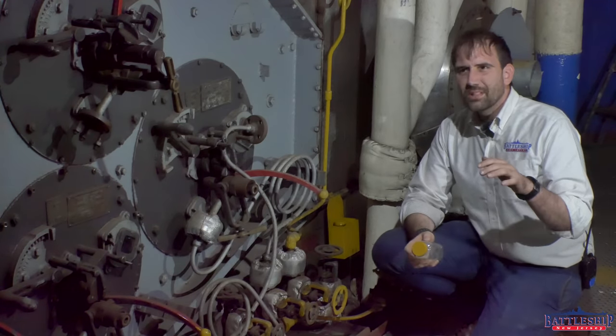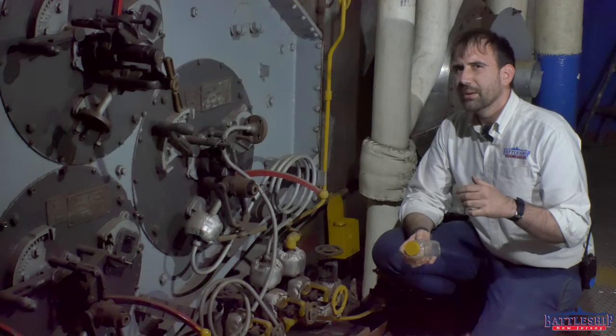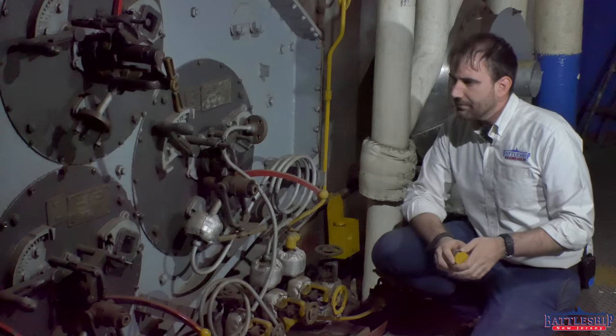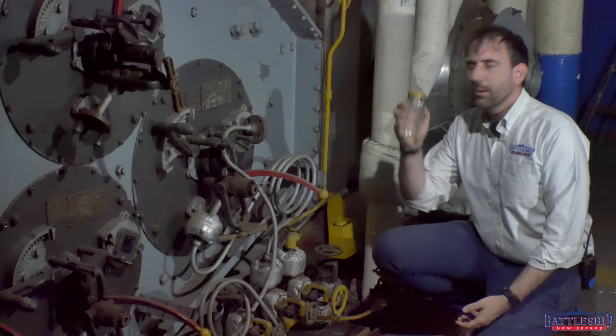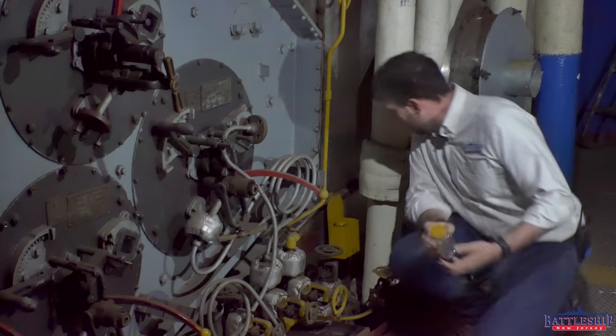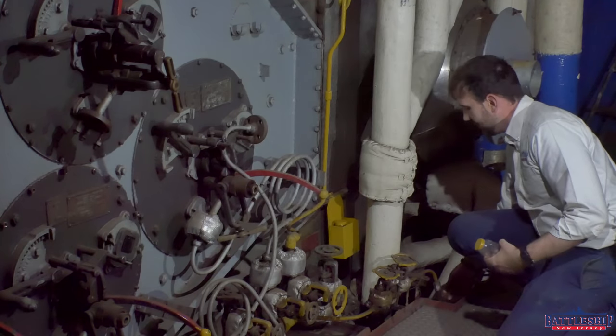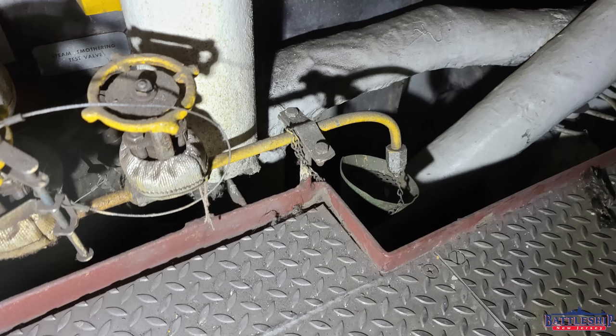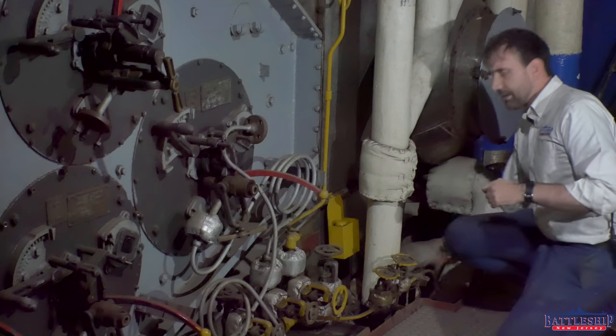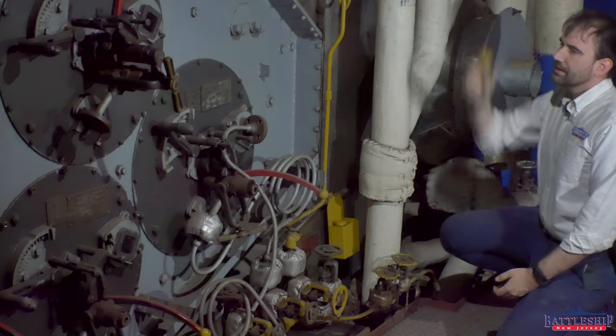I'm not sure with diesel, because diesel was so much more refined if they were still checking with that frequency, if it was a once a day thing or whatnot. So we'll just leave it at that. Why was this bottle down here? Because the place where you test it is right here. There's a valve that you remove, you get that under there, you get a sample, there's even a little drip pan down there, and then you can look at it and see if it's cloudy.